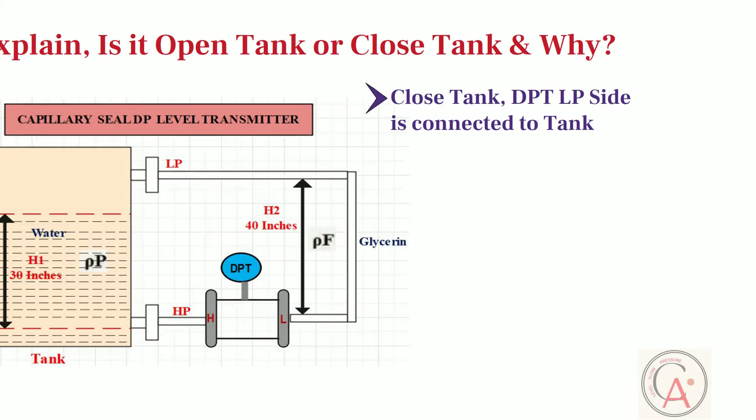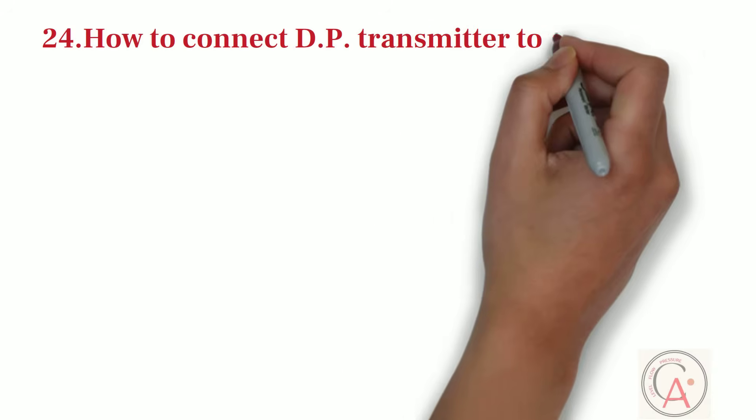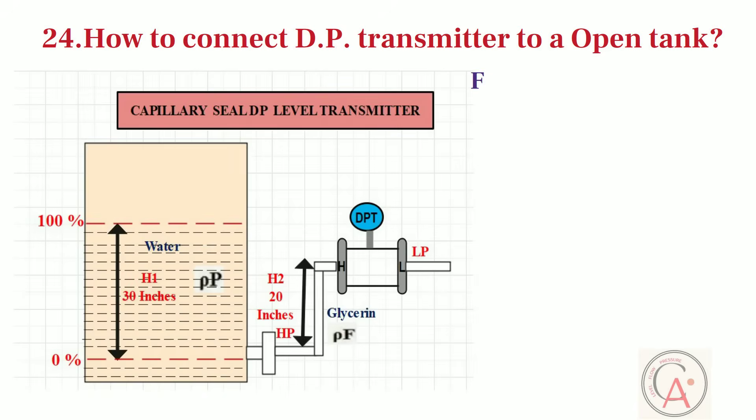Twenty-third number question is, please identify, is it open tank or close tank, and why? It is a close tank. Because DPT's low-pressure side is connected to top part of vessel. If low-port side of DPT is vented to atmosphere, then it is known as open tank. Next question is, how to connect DP transmitter to open tank? For open tank, low-port side of DPT is vented to atmosphere.